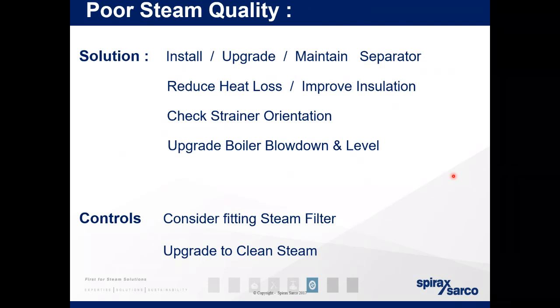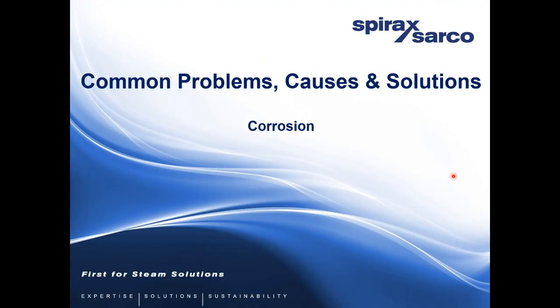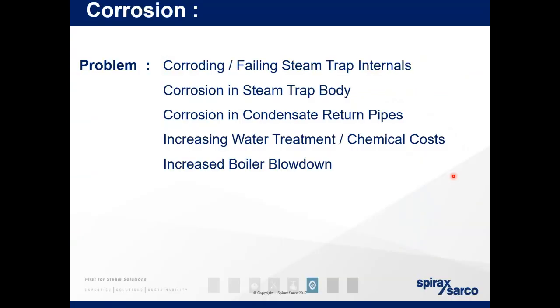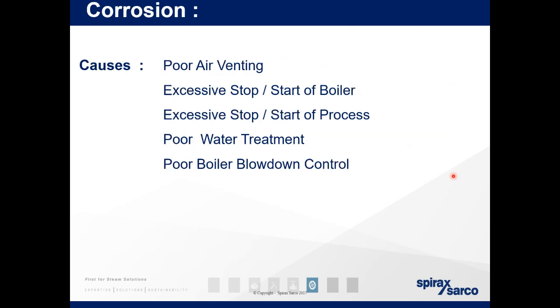Okay, some very good questions, guys, so please keep them coming. So, common problems, causes and solutions for corrosion. Corrosion in your pipes and products. The problems: corroding, failing steam trap internals, corrosion in steam trap bodies, corrosion in condensate return pipes, increasing water treatment chemical costs, increased boiler blowdown. Many of you, I imagine, would have seen some of these at some time, so we're going to cover how to solve those. The cause: poor air venting. If you've got air trapped in your system, the CO2 available there will form carbonic acid with water. That gives you corrosion.